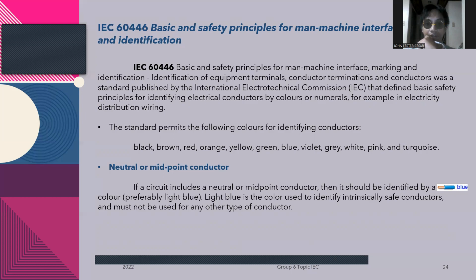The standard permits the following colors for identifying conductors. We have black, brown, red, orange, yellow, green, blue, violet, gray, white, pink, and turquoise. The colors green and yellow on their own are only permitted where confusion with the coloring of the green-yellow protective conductor is unlikely. Combinations of the above colors are permitted, but green and yellow should not be used in any of these combinations other than as green-yellow for the protective conductor.